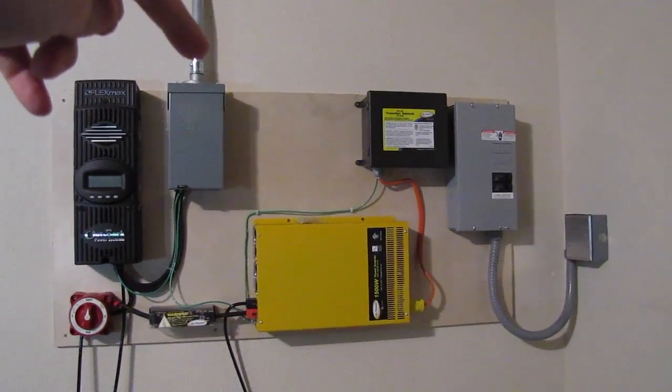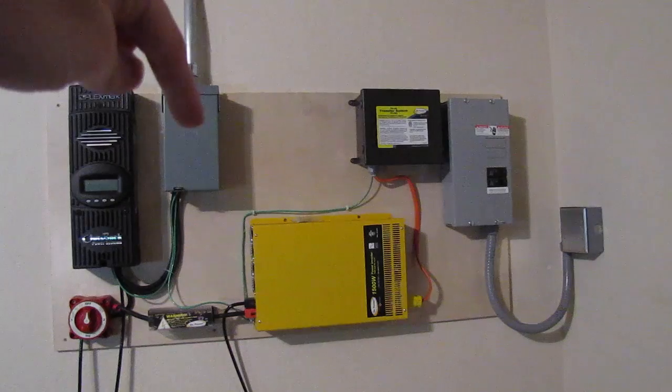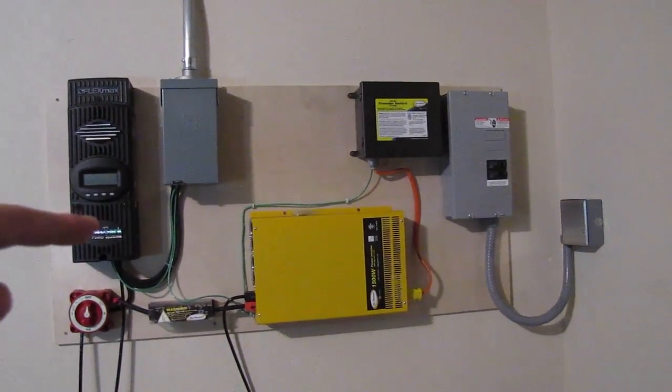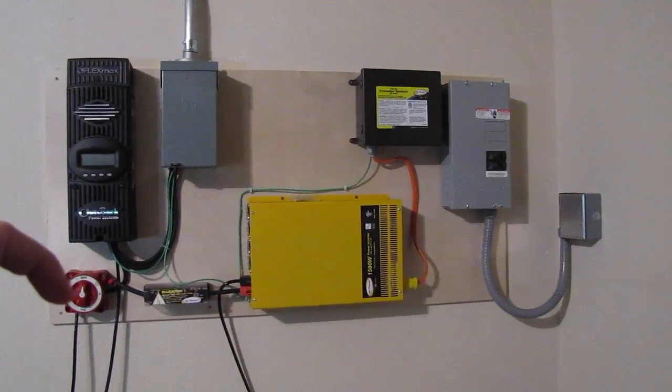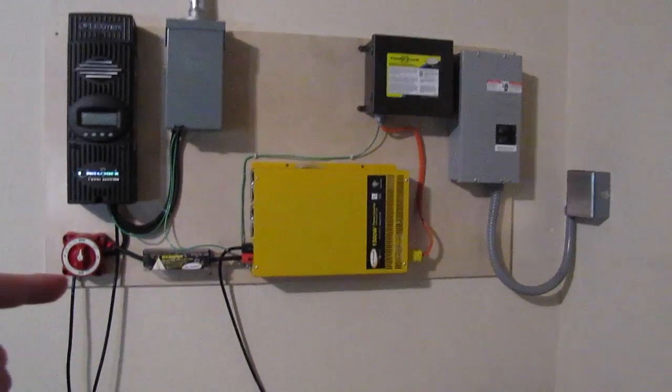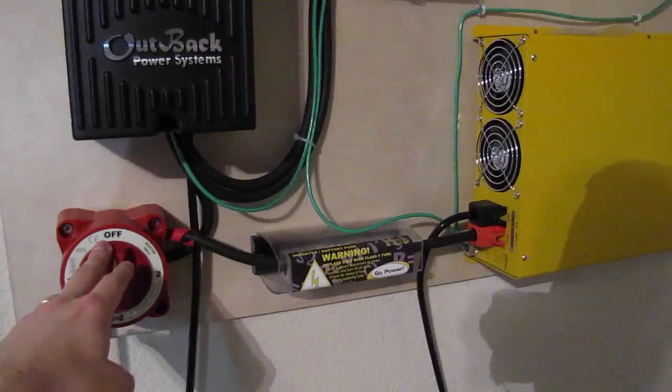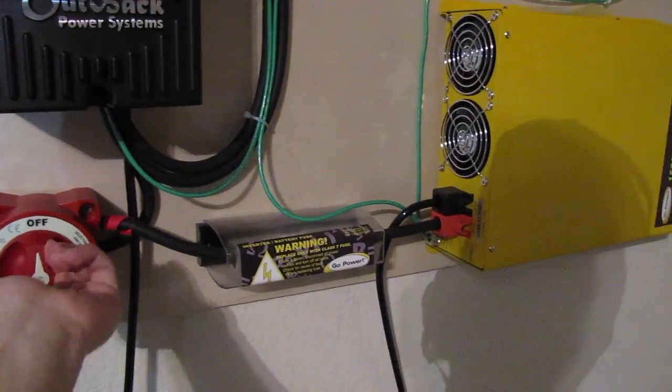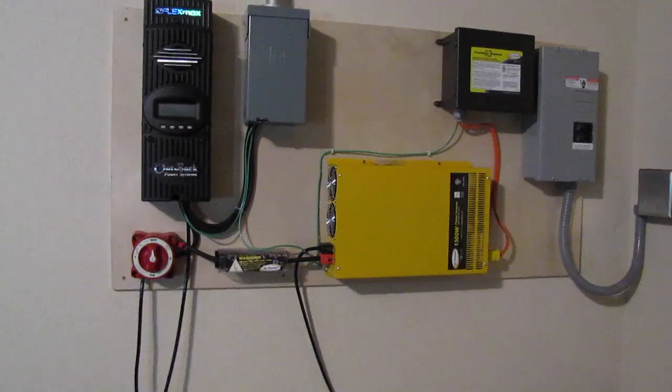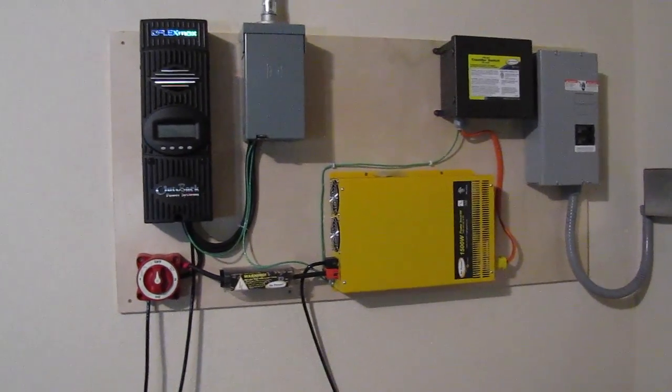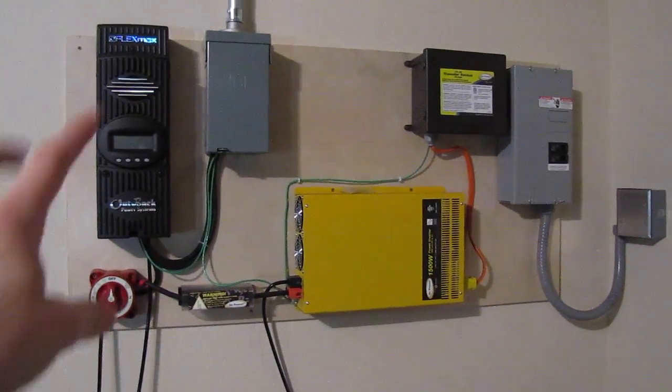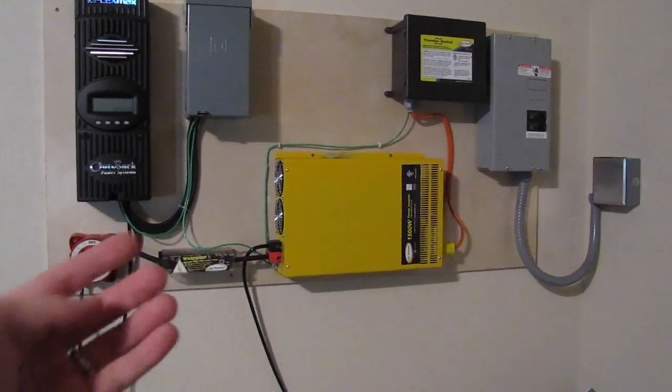You have, or I have, my solar panels coming in here to a breaker box, and that then feeds into a charge controller, and then that charge controller goes through a marine-style DC disconnect here. These are really affordable and also very effective, good beefy switches here. Then those go down on the ground to where I was keeping my batteries here on the concrete. And insert comments from people on YouTube about how I shouldn't be keeping batteries on concrete. It's actually bullshit, and they perform better because my floor helps balance out the temperature in those.